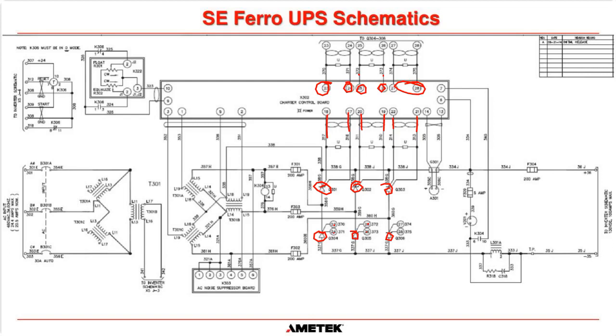So that's actually what sends a signal to the SCRs to turn them on. And that's what regulates the output of the charger. And then the final connection on that board is the feedback signal. So we are measuring the voltage feedback on these two terminals here. So this is the positive and this is the negative. There should be 135 volts in normal operation going back into these terminals here. And that's what tells the control board the feedback of the output of the system. If that goes down, then the control board says, okay, I need to send a signal to the SCRs to turn on earlier in the cycle and get more voltage to the output, and vice versa.